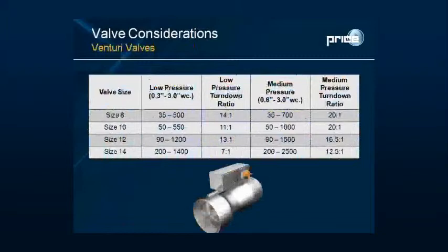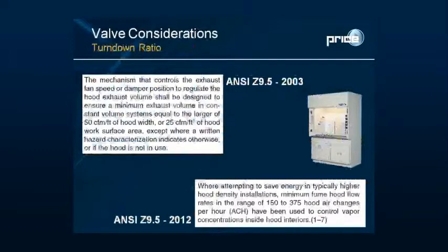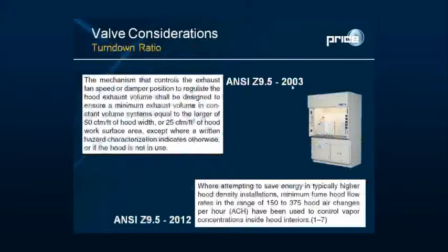To illustrate the importance of turndown, consider a code change that significantly affects fume hood exhaust. Comparing ANSI Z9.5 2003 to ANSI Z9.5 2012, the 2003 version required 50 CFM per foot of hood width, or 25 CFM per square foot of hood work surface area, as the minimum exhaust rate. The 2012 version instead references hood air changes, noting that 150 to 375 hood air changes per hour has been used successfully to control concentrations and maintain containment.